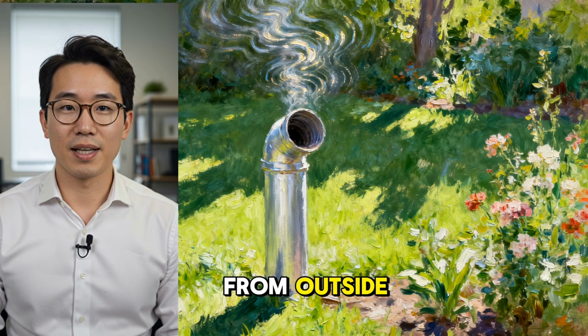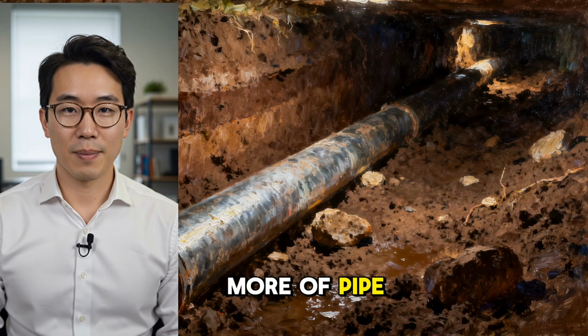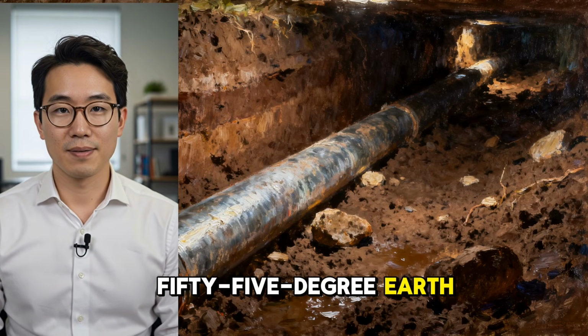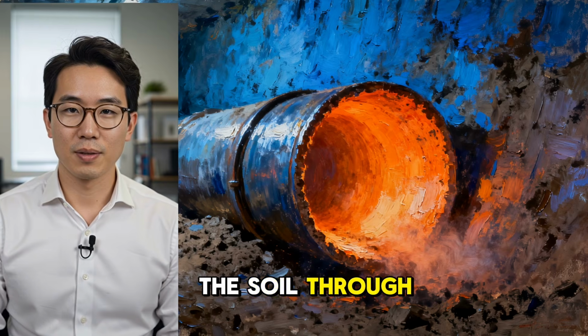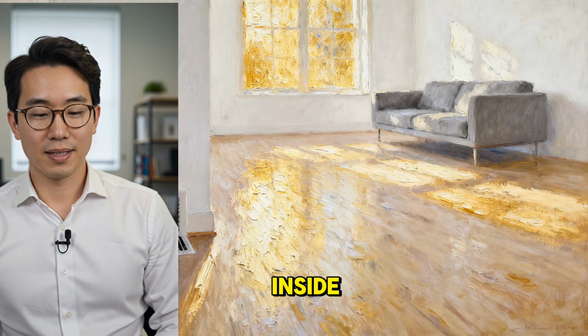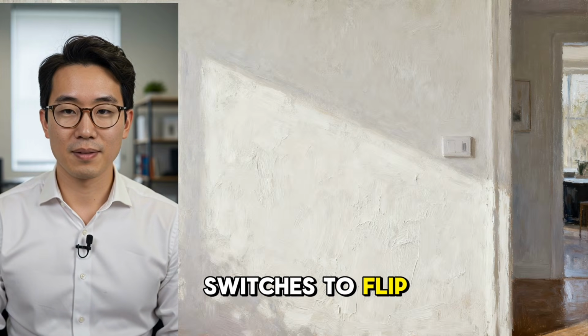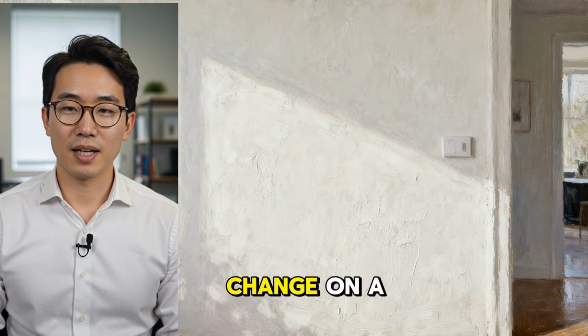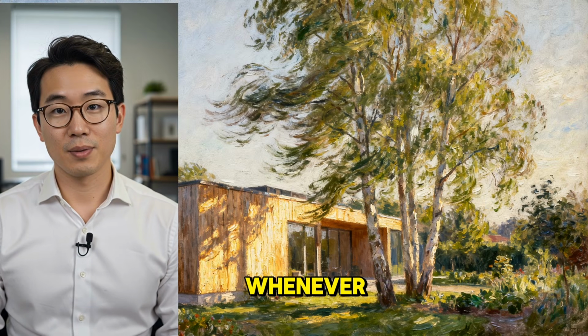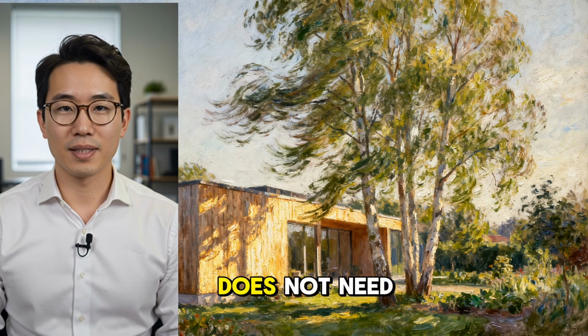Hot air enters from outside. It travels through 100 feet or more of pipe buried in 55-degree earth. Heat moves from the air into the soil through the pipe walls. Cooled air emerges inside. There are no switches to flip, no settings to program, no filters to change on a schedule. The system runs whenever air moves through it and does nothing when it does not need to.